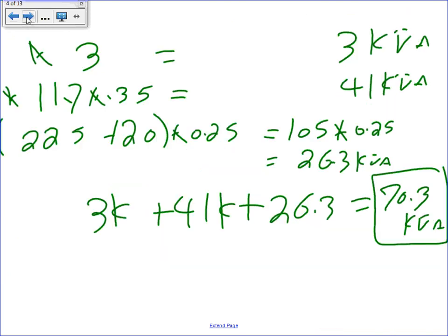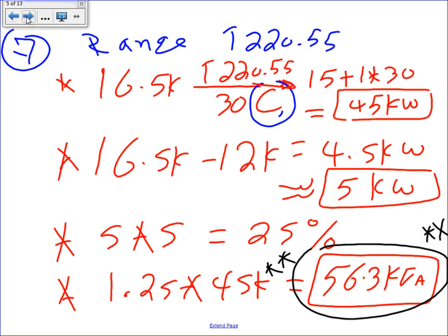Go to next. Okay, this one we didn't do much here yet. Let's go all the way to the range. For the range, here's what you guys are going to do. I'm going to do it in green. I'm going to say neutral, and I'm going to take 70%, 0.7 times this number, 56.3K, and I need my friend to give me the 70%, and I'll tell you where this comes from. This is coming for the range from 220.61(B), for the neutral, 70%.